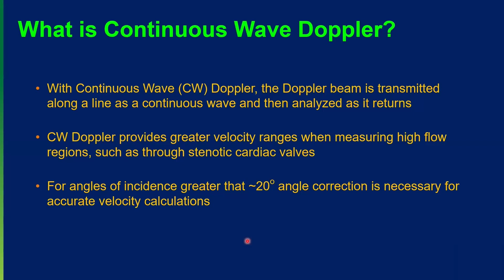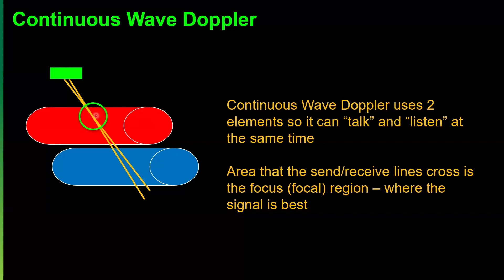So when we look at continuous wave Doppler, again, there are two elements in here. One constantly talks, one constantly listens. Whereas when we do pulsed wave, it's done in pulses, just like the name says. So we're using the same element. It sends the sound out and waits for it to come back. With the continuous, it's a continuous sending of sound, and the other one is continuously receiving it. The area where the lines cross is called the focal region, or focus region, and that's usually where we'll get our best or strongest signal. I don't mean the most accurate, but if your system has the ability to do this, that's generally where we're going to find our best signal.